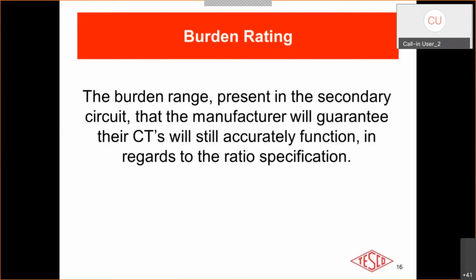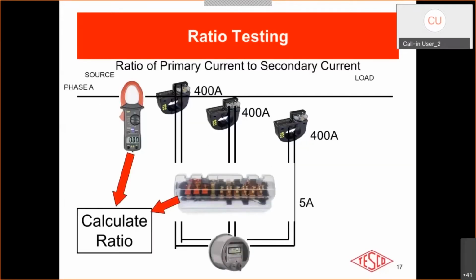The burden specification is a little more detailed than the ratio specification. The burden range present in the secondary circuit that the manufacturer will guarantee their CTs will accurately function in regards to the ratio specification. And we'll get back to how to test that specifically. So for a ratio test, it's pretty straightforward. You just take a measurement of the primary current, a measurement of the secondary current from the CT, typically through the safety test switch, and calculate the ratio.